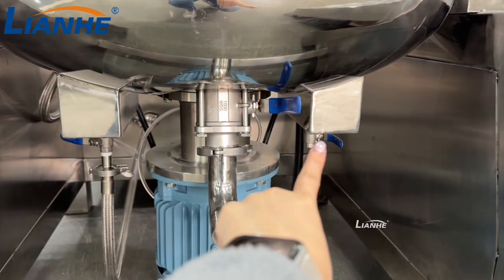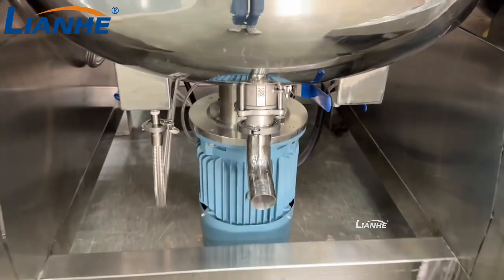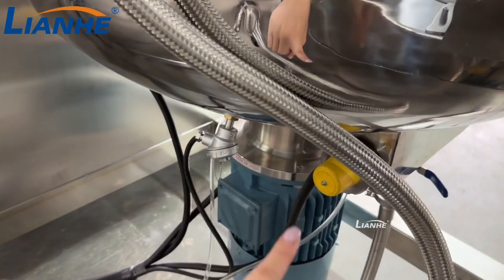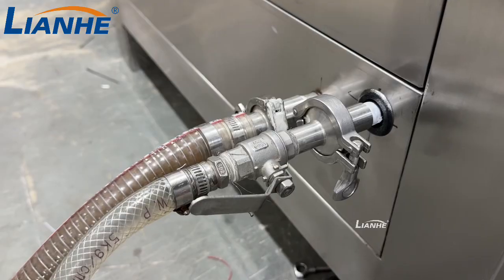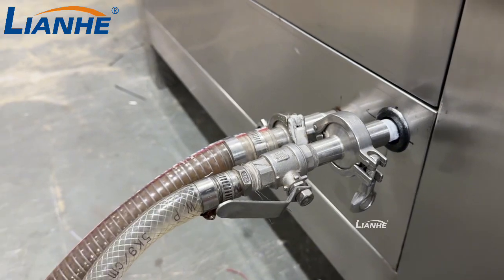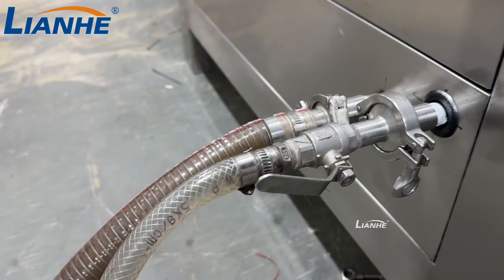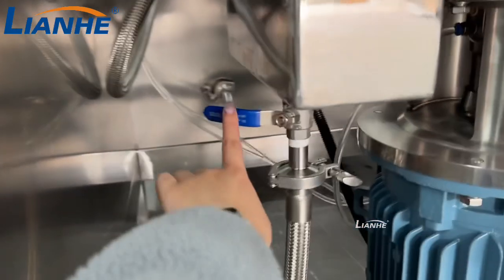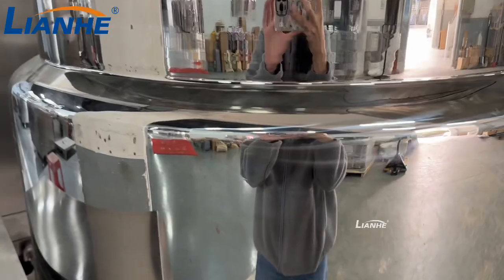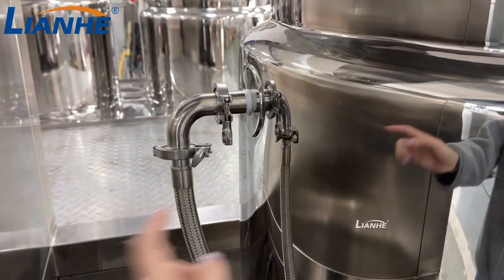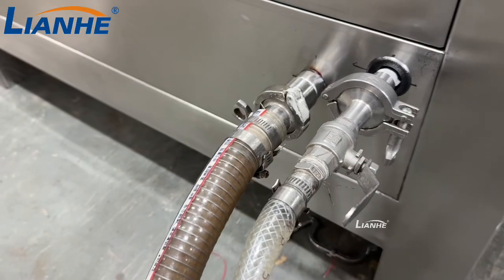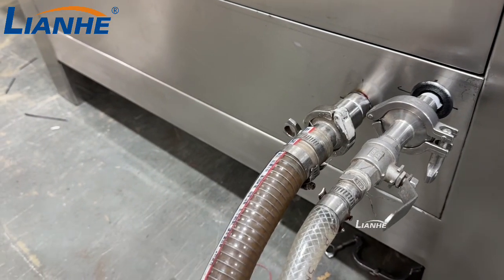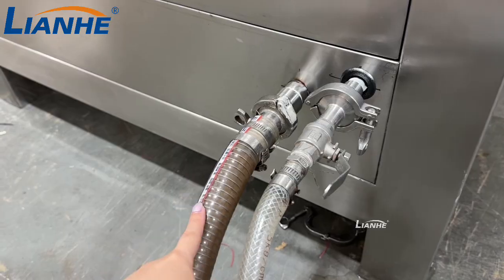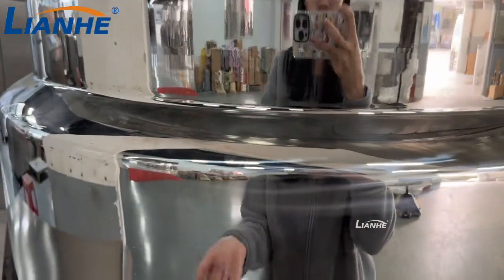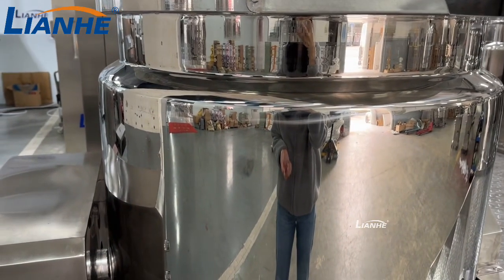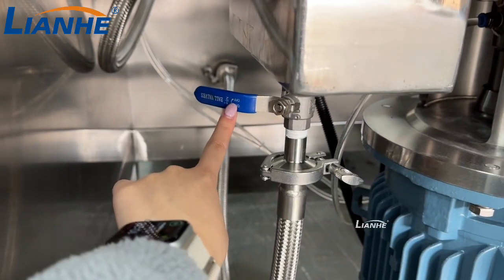And you may check this, too, is the heating rod, and then I will tell you how to use the electric heating. You may check here are the 2 heating rods here. When you need to use the heating function, first of all, keep this valve open all the time. Let the tap water inside it. Open this valve to let the tap water inside the jacket. When this jacket is full of water, the water may come outside from here. And then you may see the water will come outside through here. When the water comes outside from here, it means that this jacket is full of water, and then you can use the heating function. And then you can turn off this water inlet valve.